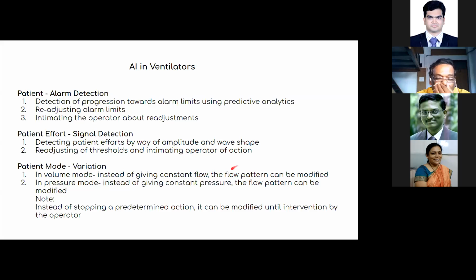Right now, the constant flow is being given. My view is that the flow pattern has to be understood and the flow has to be adjusted accordingly for giving the preset volume. That will make the machine more intelligent. The second mode is, and here the problem is, when you give a constant volume, if you give more volume than the lungs can withstand, the pressure will go on increasing. So when you are giving a volume mode, you have to constantly look out for pressure and be alert that the pressure should not go up.